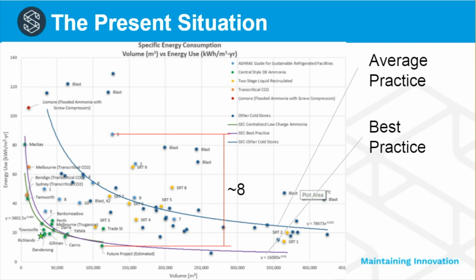And then I've taken a really bad system here, more or less in the middle of the picture, and compared that with a very good system down the bottom of the picture. And you can see there that the difference in specific energy consumption, or SEC value, is a factor of 8. And this is at the high end of what is normally seen in practice. Normally, the difference between best practice and average practice is in the order of between 1.4 and 4 times.